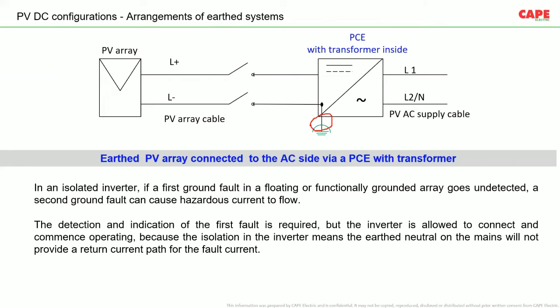Now, whenever there is a fault on the PV array, between the PV array or the lines and an exposed or extraneous conductive part, we have to ensure that the earthing arrangement is made in such a way that the fault current returns to the source through this path. This path means through that particular fuse. Let's say a 1 ampere fuse, up to 25 kilowatt solar PV. A fault current of less than 1 amp is not hazardous, more than 1 amp is hazardous.